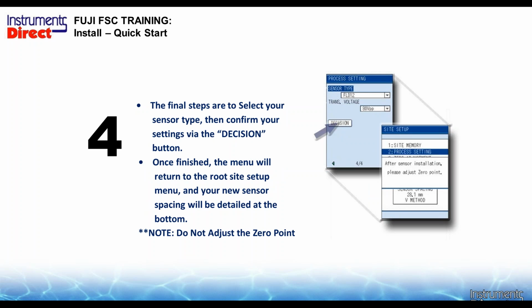And then you have the trans voltage. There are 4 different settings of the trans voltage. Basically, as we send them out, we set them on the 2nd position. The only time you'd actually change the trans voltage is if you didn't get a signal, and that may occur on a nasty, nasty old pipe application. When you need a little more boost, that's the time you want to bump it up to the 4th position to try to get a reading. No, don't leave it set on the 4th position all the time, because the more pinging you do with the crystal at high power, it will degrade it at some point in time.